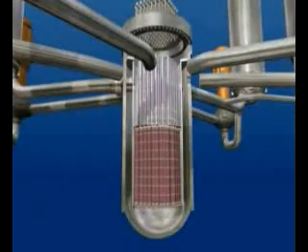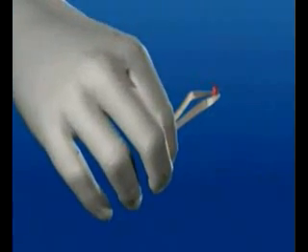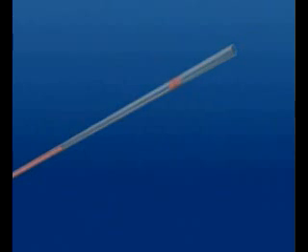The energy production process begins with the fission of uranium atoms inside the reactor core, which contains nuclear fuel assemblies. Each of these assemblies contains several hundred sealed tubes, each containing pellets of enriched uranium — enriched because it contains a high proportion of uranium-235, the fissile element.